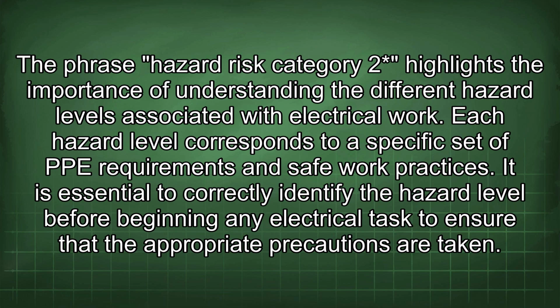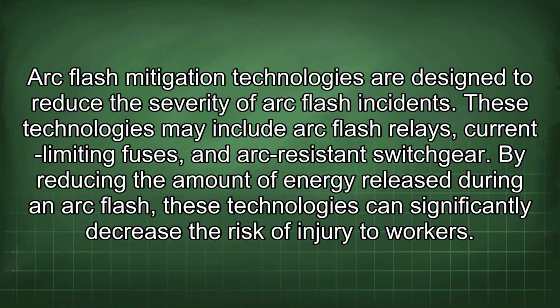The phrase hazard risk category 2 asterisk highlights the importance of understanding the different hazard levels associated with electrical work. Each hazard level corresponds to a specific set of PPE requirements and safe work practices. It is essential to correctly identify the hazard level before beginning any electrical task to ensure that the appropriate precautions are taken. Arc flash mitigation technologies are designed to reduce the severity of arc flash incidents. These technologies may include arc flash relays, current-limiting fuses, and arc-resistant switchgear. By reducing the amount of energy released during an arc flash, these technologies can significantly decrease the risk of injury to workers.